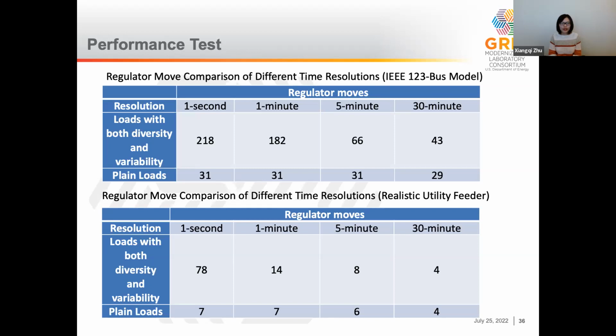The two tables here show the comparison of voltage regulator operations between the loads with both diversity and variability and the plain loads. As time resolution goes from 1 second to 30 minutes, we can see the variability modeling effectively gets eliminated due to heavy averaging, and the impact of the diversity model becomes isolated and remains. In the case with both diversity and variability, improving the time resolution from 30 minutes to 1 second increases the number of regulator operations captured.